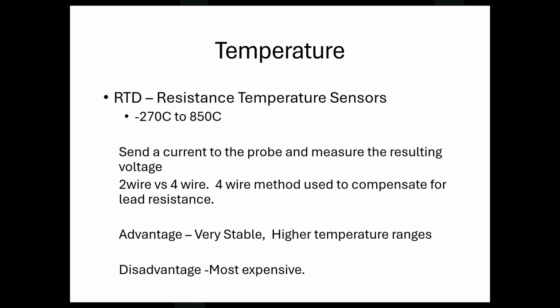Does your multimeter measure resistance? Nope. Ah, gotcha, you went too soon. A multimeter cannot measure resistance, a multimeter calculates resistance. I know, it's a trick question, that'd be a good one to put on the certification exam maybe. Because what we do, we put in a current, we measure a voltage coming back, voltage over current equals resistance, Ohm's law. So your multimeter, if you ever want to get people on that, does not actually measure resistance, it calculates it.